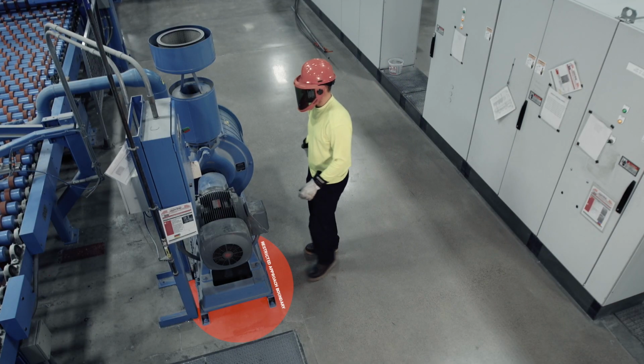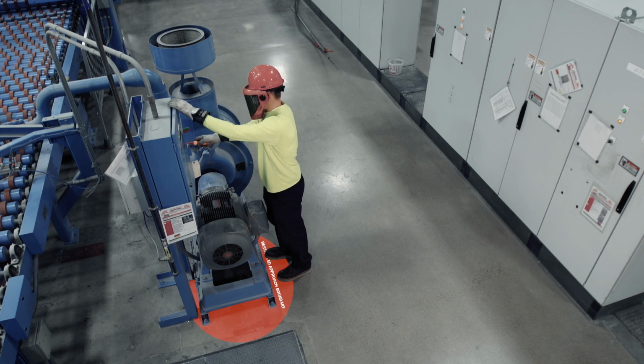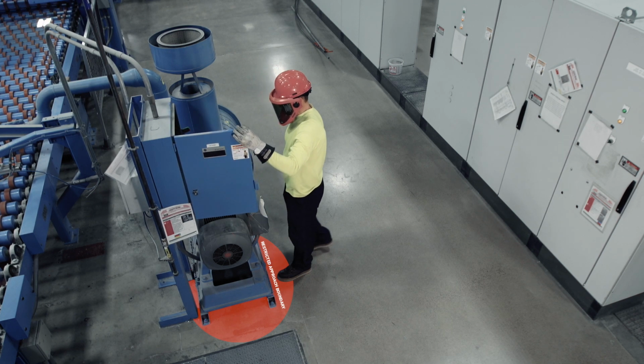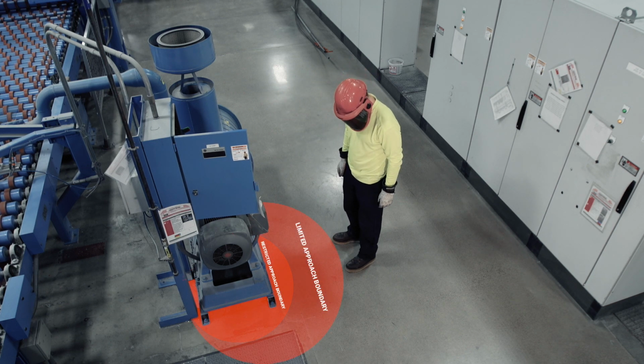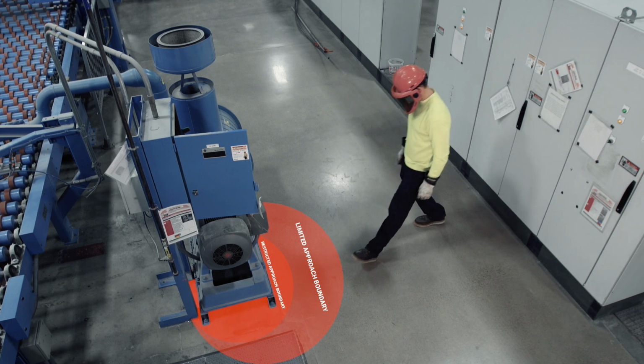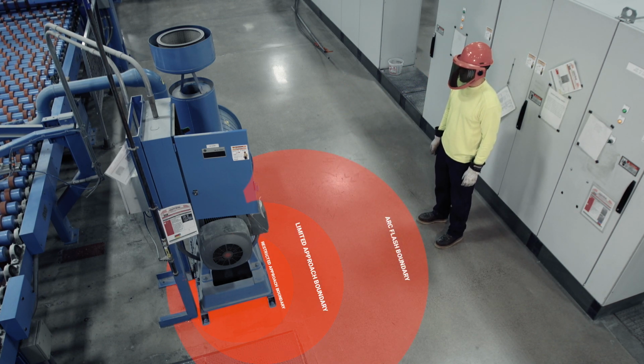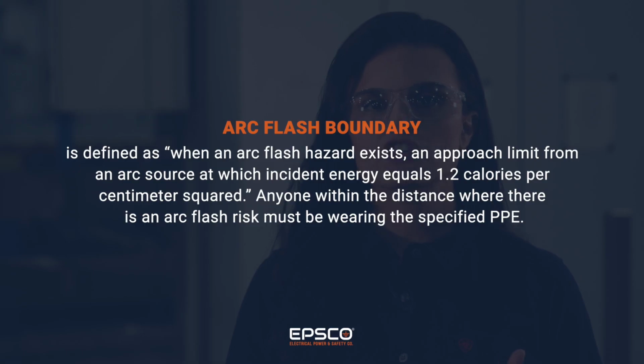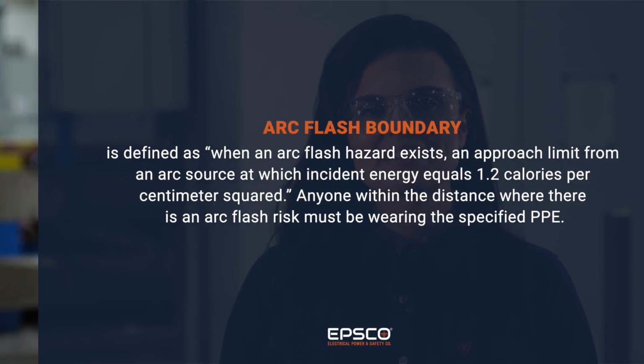an electrical arc event. Keep in mind that an arc flash study alone won't estimate the likelihood of an event occurring in each specific case. What it does do is specify working boundaries. There are 3 you'll need to know: the arc flash boundary, the limited approach boundary, and the restricted approach boundary. Arc flash boundary is defined as, when an arc flash hazard exists, an approach limit from an arc source at which incident energy equals 1.2 calories per centimeter squared. Anyone within the distance where there is an arc flash risk must be wearing the specified PPE. The other 2 boundaries are independent of arc flash boundary. The aim of both is to reduce the risk of electrical shock.